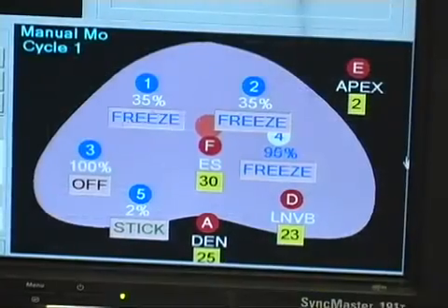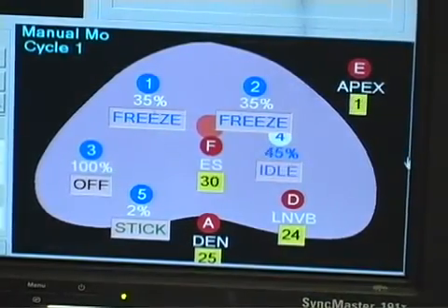And we can probably turn probe 4 on if we see the temperature continue to decrease. Probe 3, which is on the right side of the gland, is still at 16 degrees.